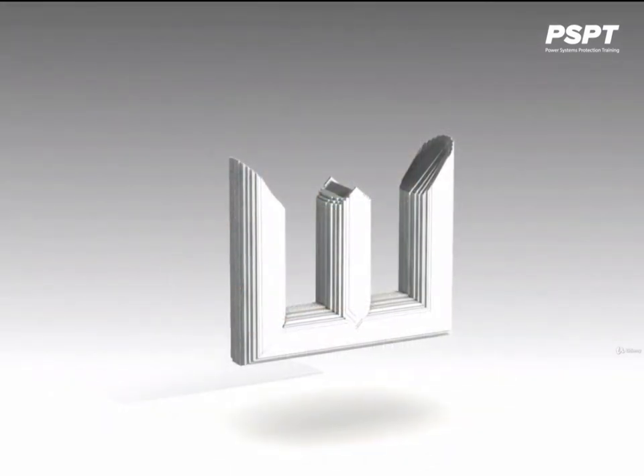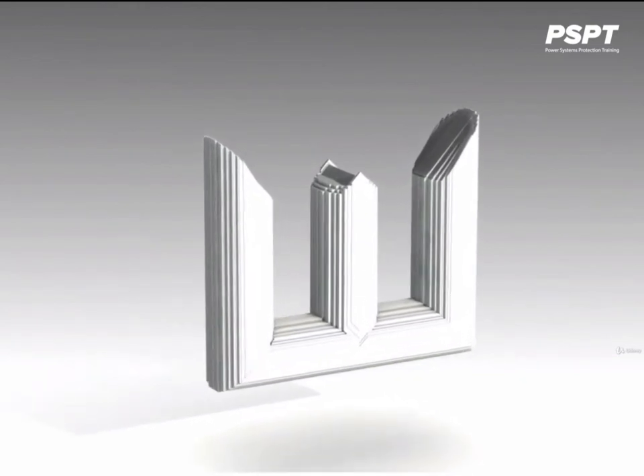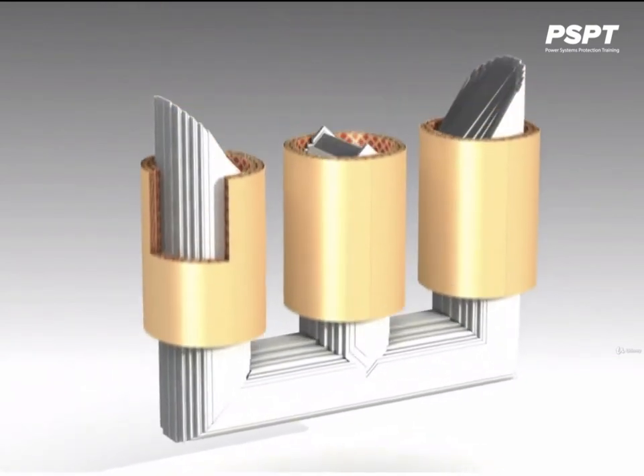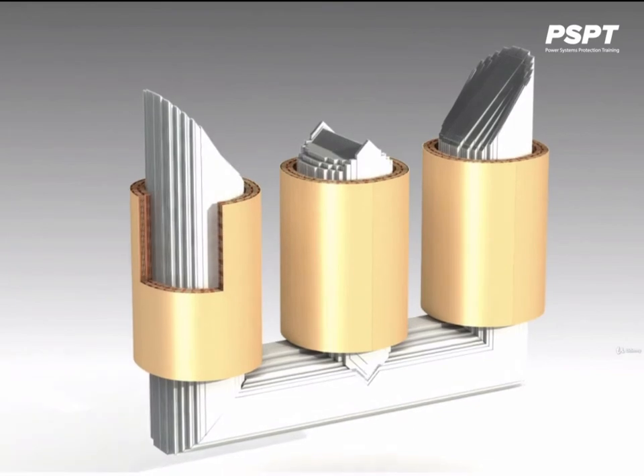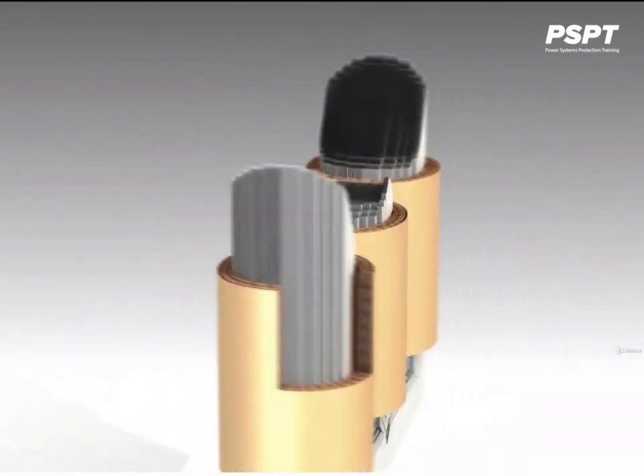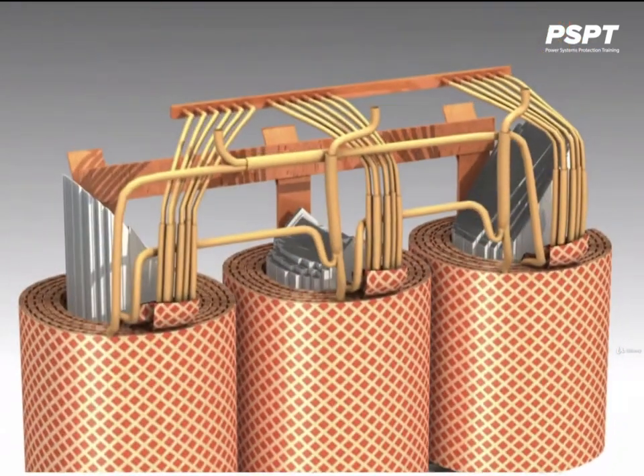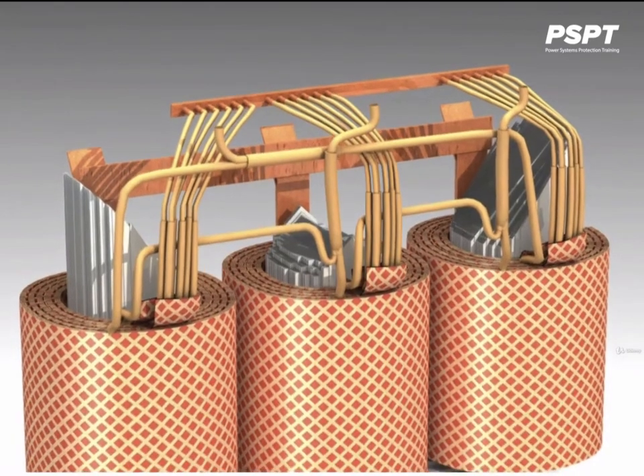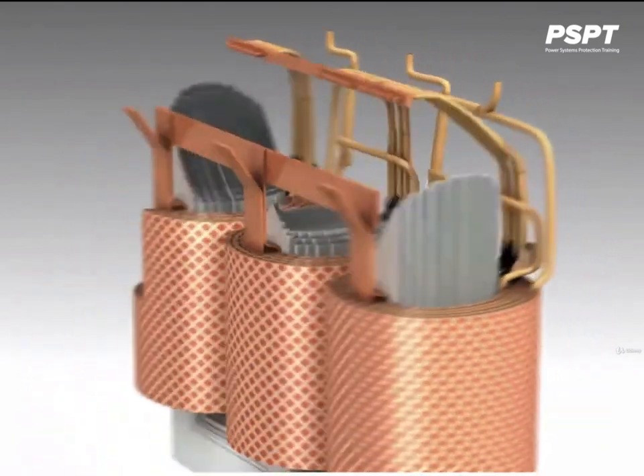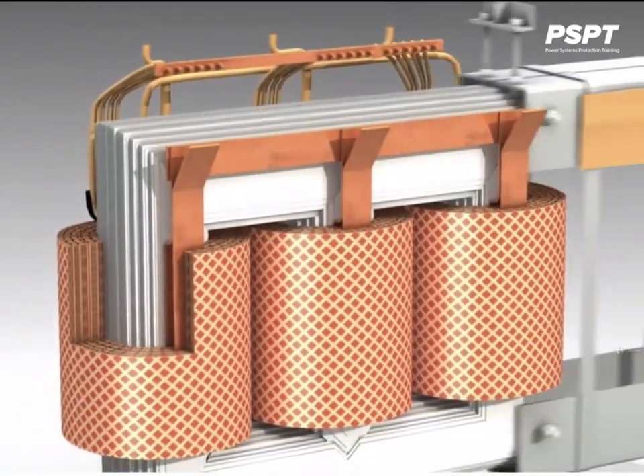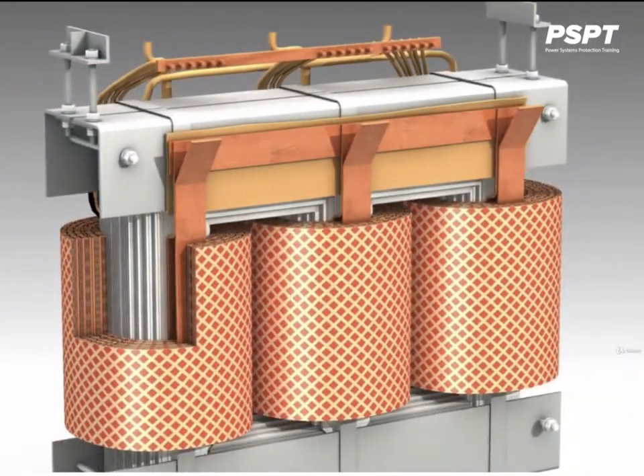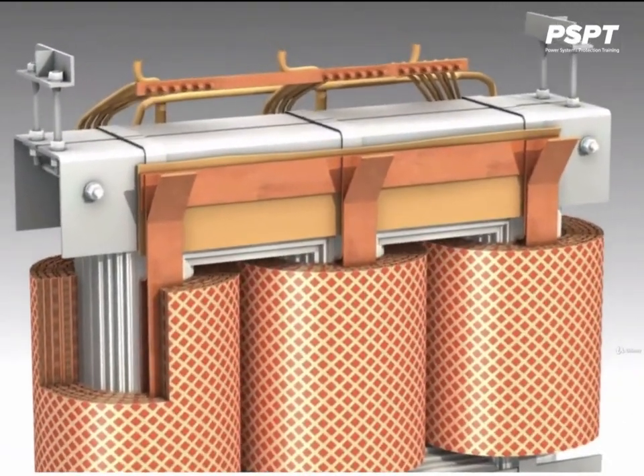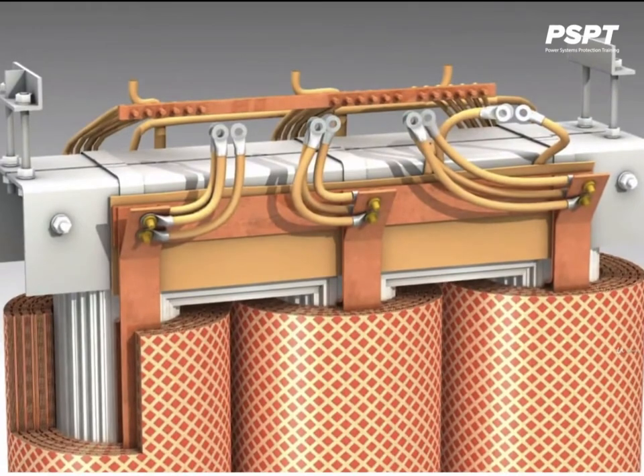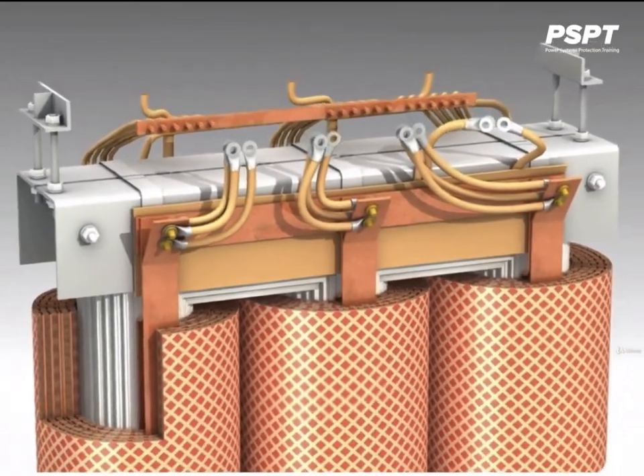Starting with the laminated iron core, which is open at this present time to receive the low voltage windings first, then the concentric high voltage windings with the leads bringing out the connection. The top part of the laminated core is then put on. The leads for the low voltage are connected.